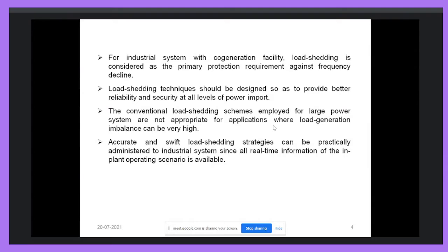So they have to maintain balance between load and generation. For that, they require a reliable load-shedding technique. We know the load-shedding techniques, I think you are aware of them. Under frequency relays are the relays used to protect the system from under frequency, and these relays are also used to disconnect load whenever the frequency decreases below a particular value. But they are not accurate.